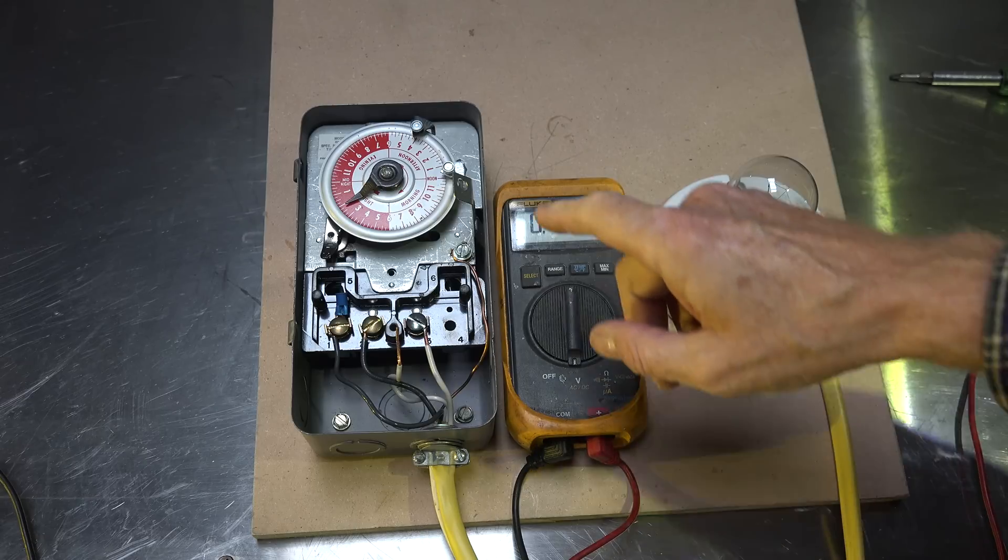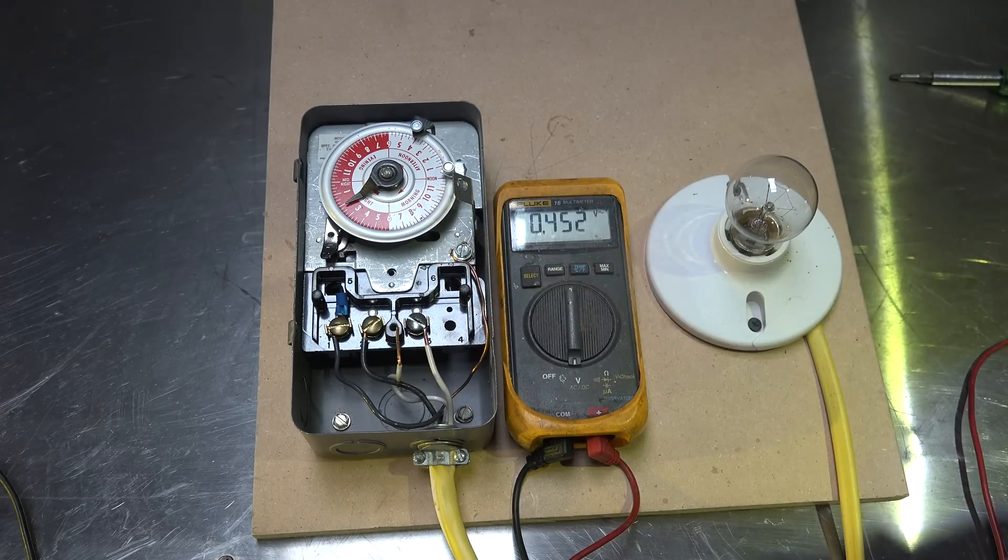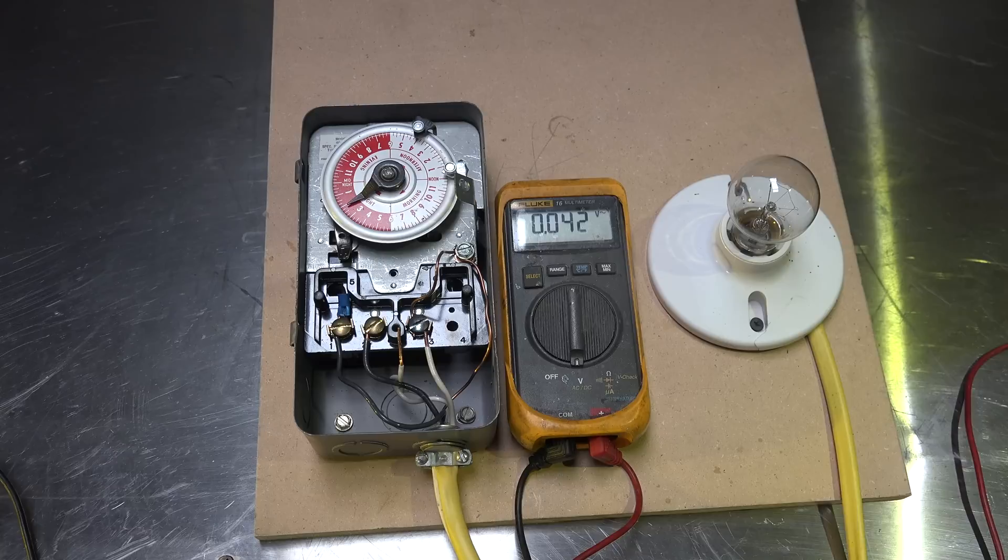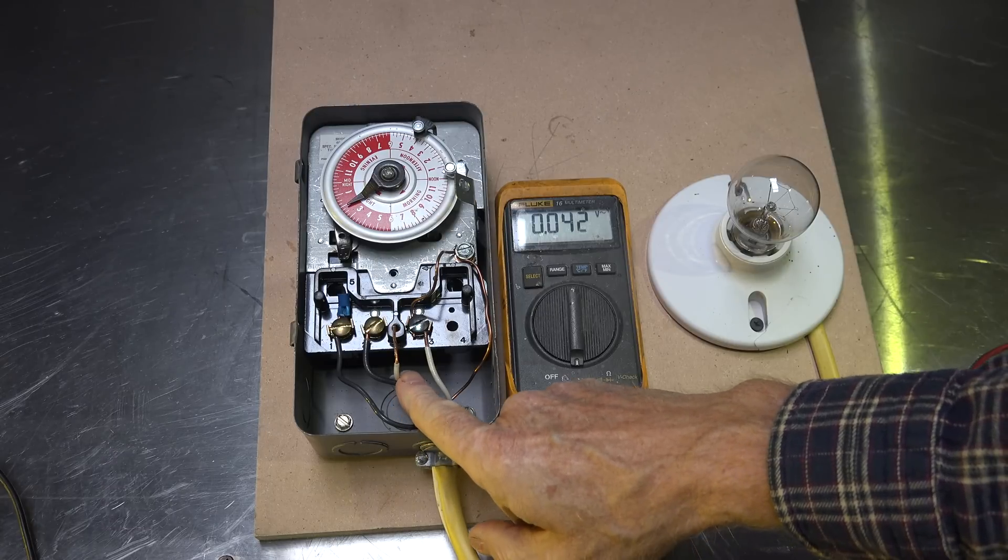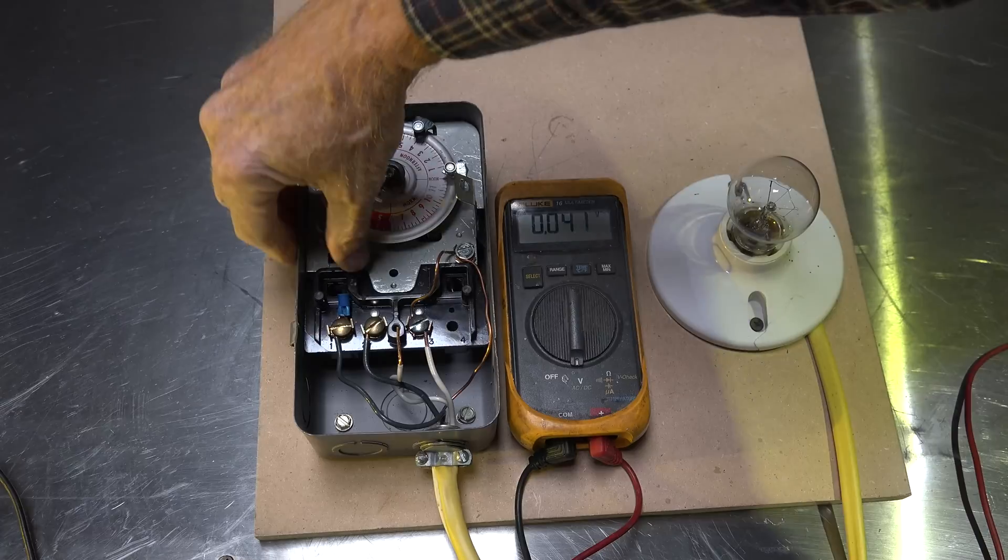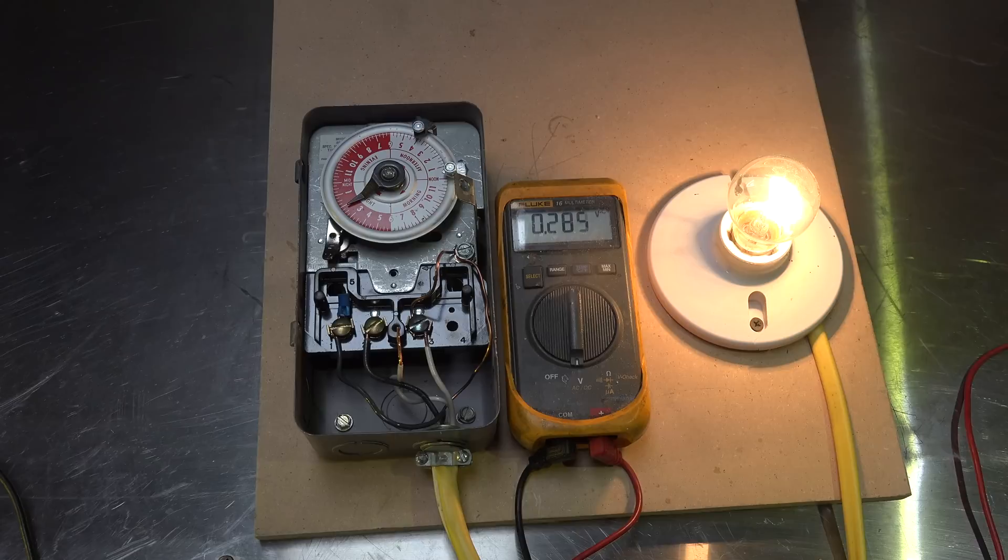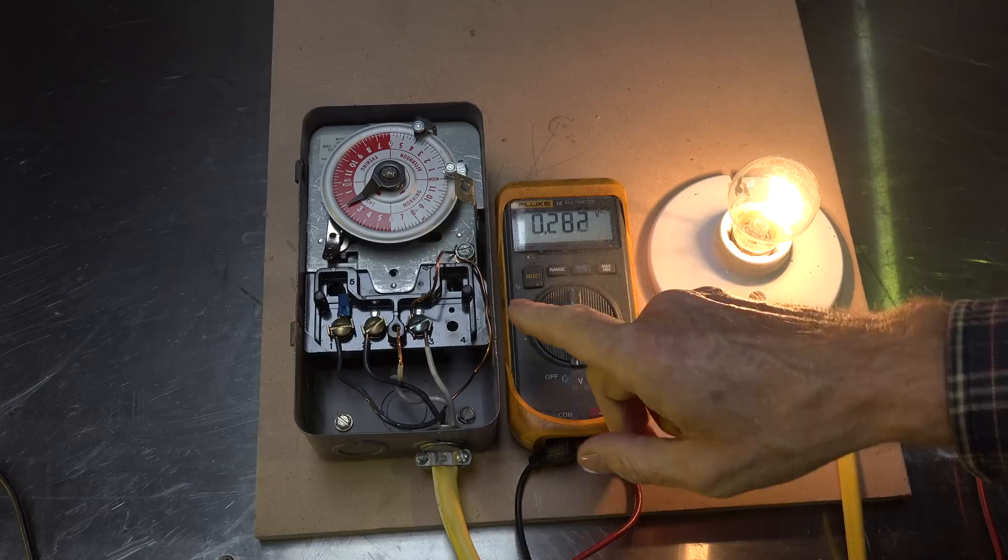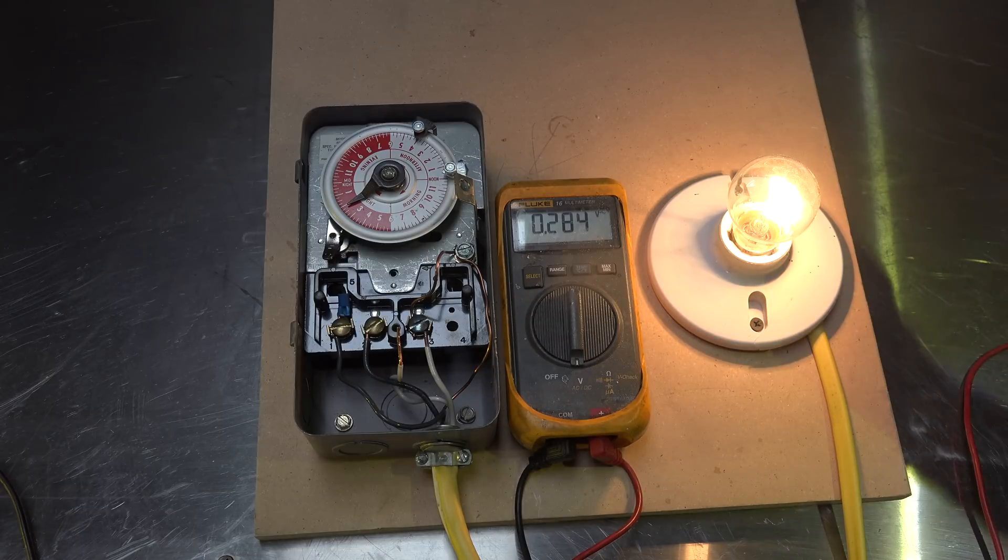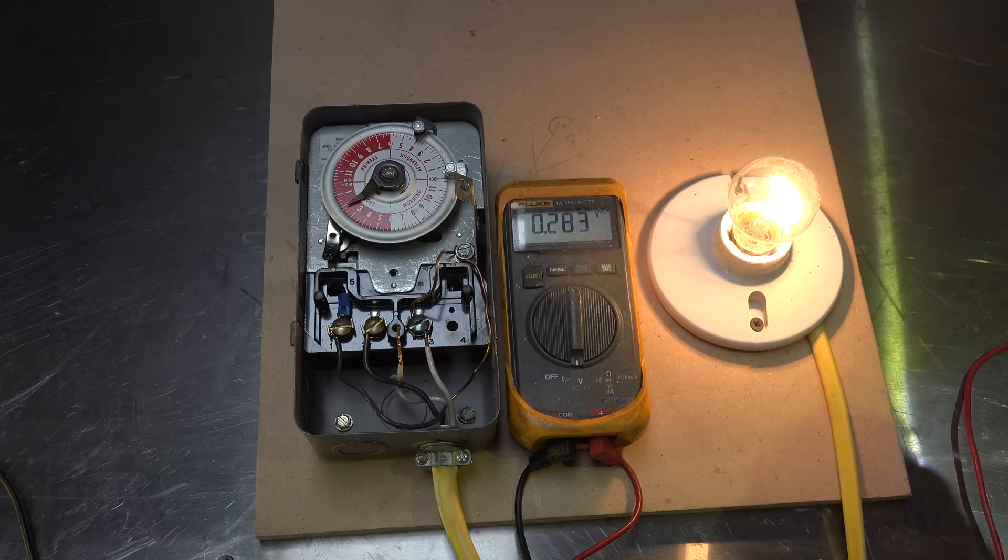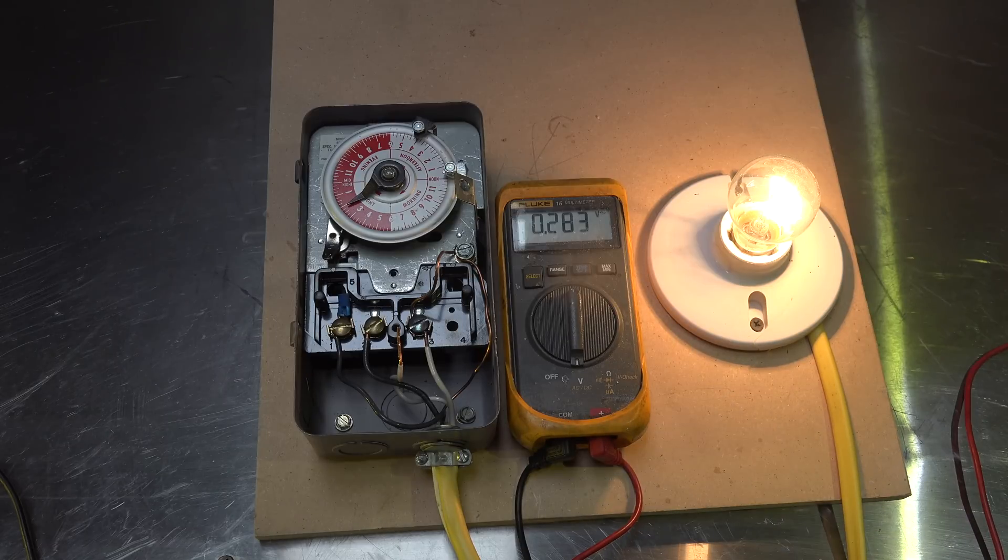Now this is with the ground and the neutral separated. Now let's hook them together. Note I've removed the neutral wire. Okay, the light works. Now some might say that's a good idea, but it's really not because the ground wire is what I call a virgin wire. The virgin wire should never carry power through it. There's too many problems with carrying power through ground.